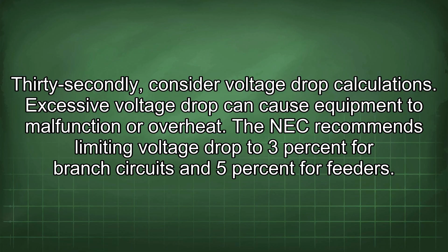32nd, consider voltage drop calculations. Excessive voltage drop can cause equipment to malfunction or overheat. The NEC recommends limiting voltage drop to 3% for branch circuits and 5% for feeders. Understanding how to calculate voltage drop is essential for ensuring that equipment receives adequate voltage.